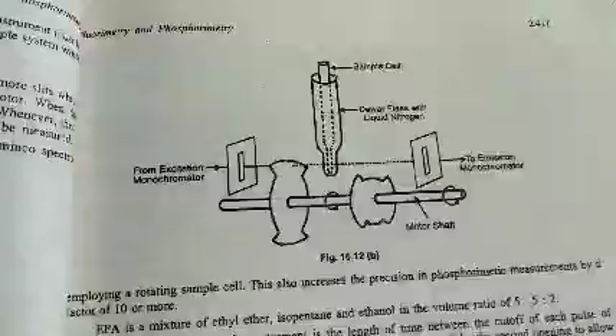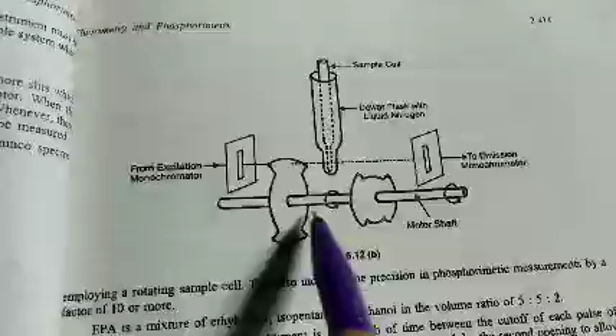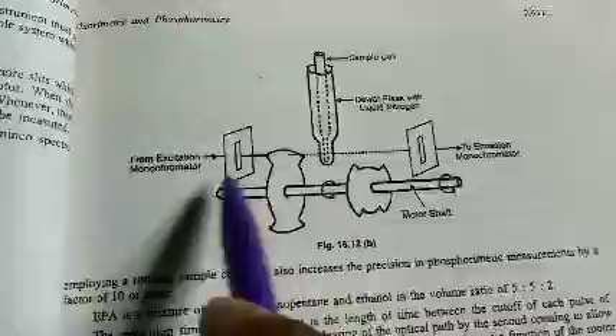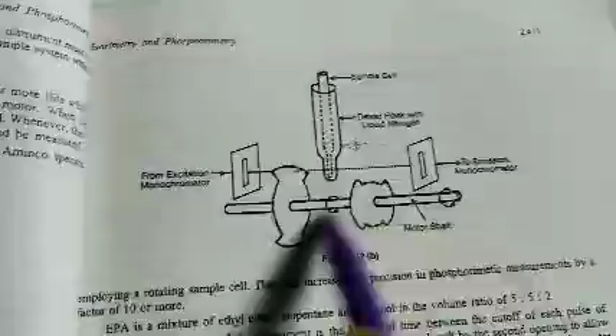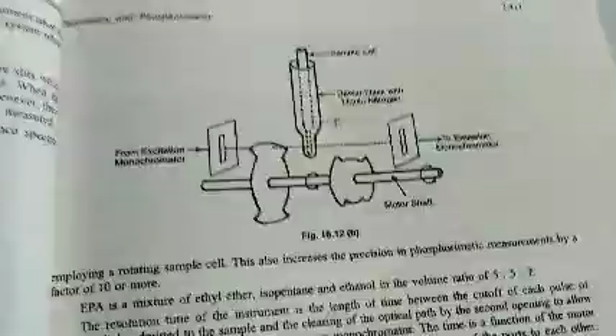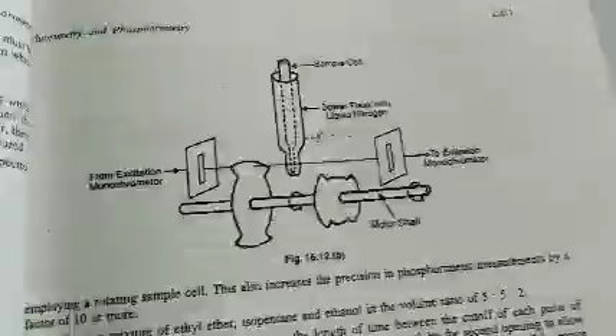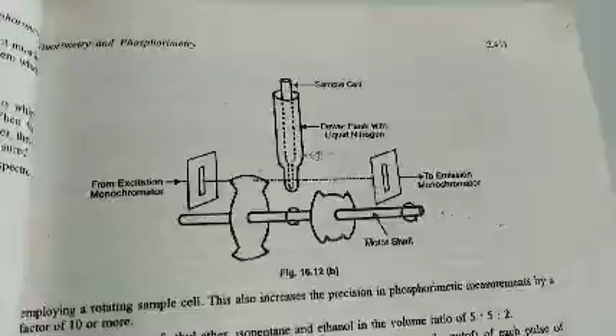The second is the Becquerel rotating disc. The Becquerel rotating disc consists of a motor. Here the source comes in, and two discs are moving in the upward and forward direction. It contains a sample cell and a Dewar flask. Here the Dewar flask is fixed and the discs move. Then, as in the fluorimetry instrument, a detector is attached. The light source generally used is a mercury lamp.